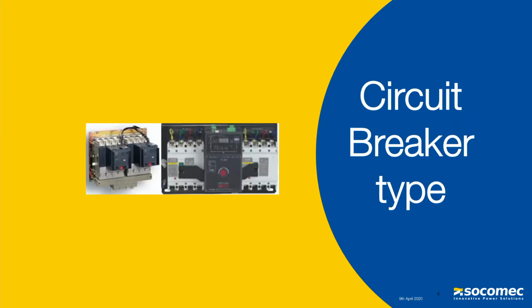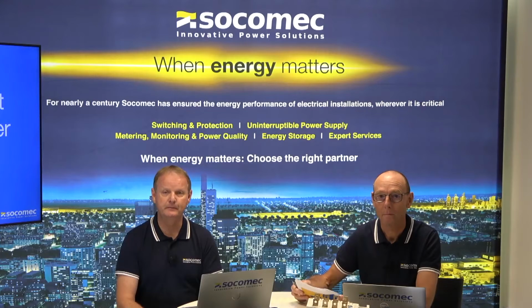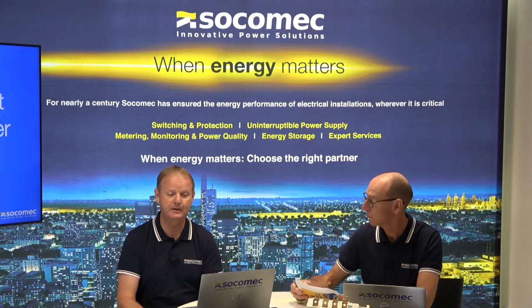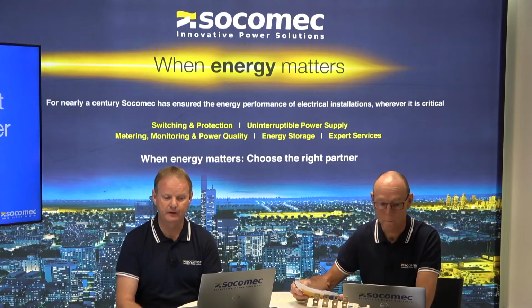And here are some more images of a circuit breaker type, which is also not allowed under BS 8519 for life safety services. However, just for clarification, you can use either of these, contactors or circuit breakers, for other transfer switching applications, but not for life safety services.